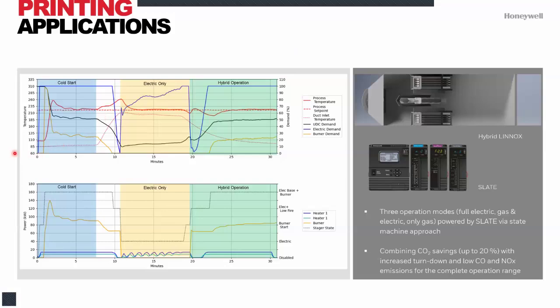Up here you see, at the time we simulate a cold start, we enable electric heaters that can kick in right away, and then there's a slight delay: safety check, pre-purge, burner goes into operation, temperature rises, we stabilize. The black line is our demand signal coming from a temperature controller - it's just a simple 4 to 20 milliamp signal.